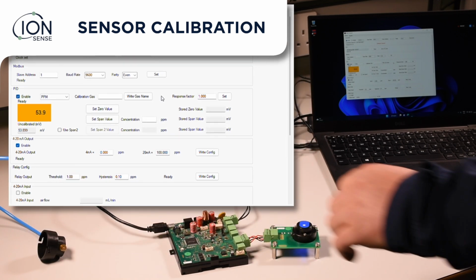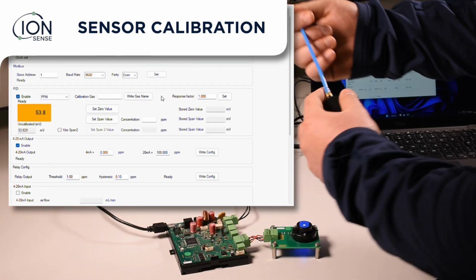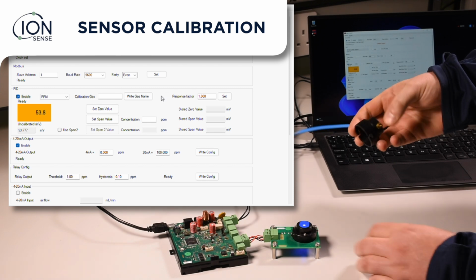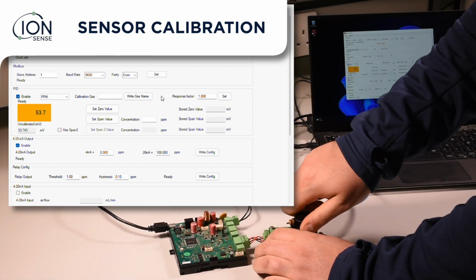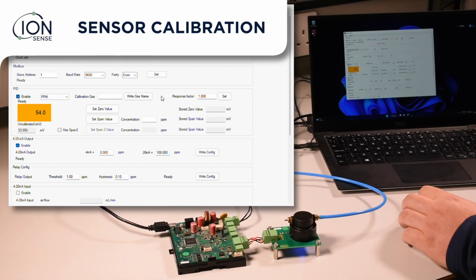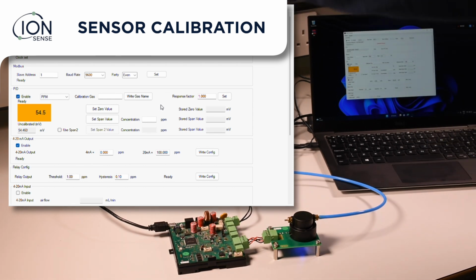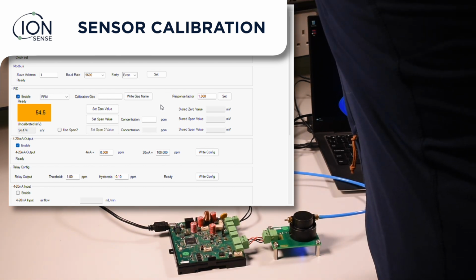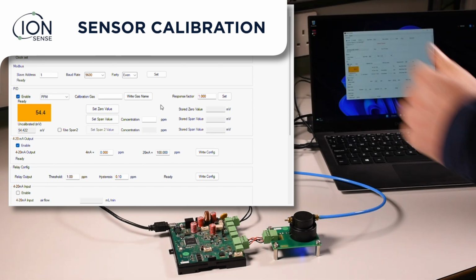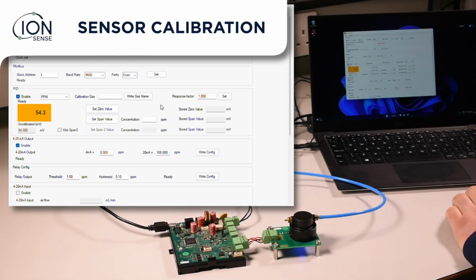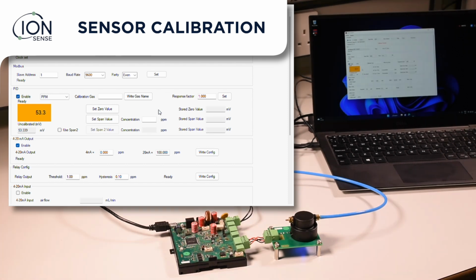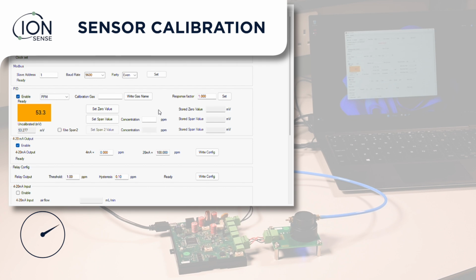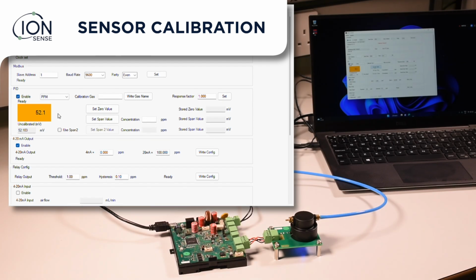Now connect the zero gas to the gas delivery hood. Now turn the gas on. After a few moments the reading will start to drop. If the MiniPID has been switched off for an extended period, it may take a few minutes to reach a stable level. Once the zero level is stable, click the Set Zero Value button.